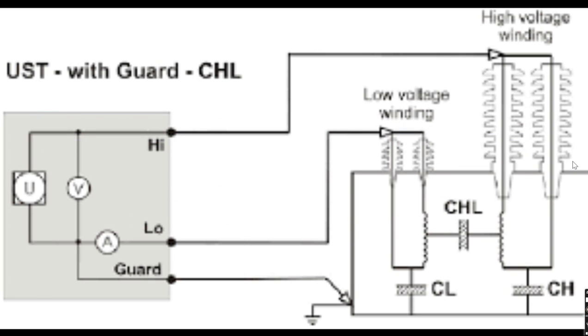This USTG mode of testing is also used in the case of transformers for finding out the value of insulation between two different windings. This is the schematic diagram of a three-phase two-winding transformer for carrying out tan delta testing to find out the insulation between the windings of the transformer.